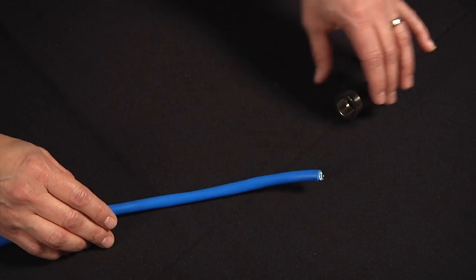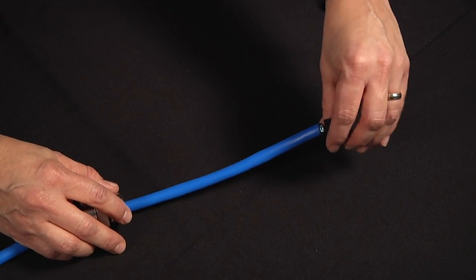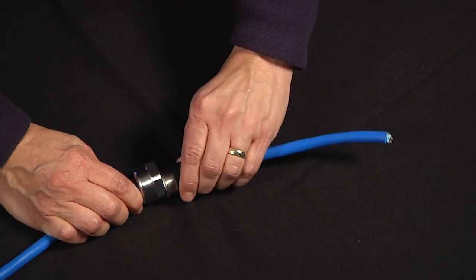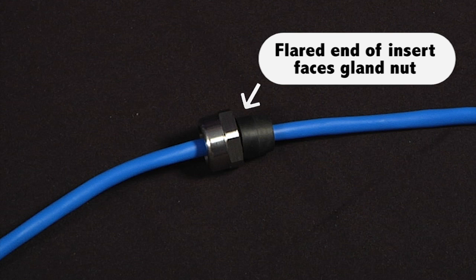Next, slide the gland nut onto the cable, followed by the insert. Make sure the nut and insert are on the cable the right way. The nut has to be able to screw onto the gland body when everything is put together. The flared end of the insert should be facing the nut so that the insert fits snugly inside the nut.